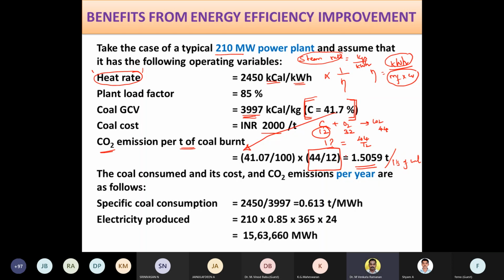Now, the heat content of the coal is 3,997. The heat rate required is 2,450, accounting for all efficiency factors. So the quantity of coal I should supply is based on 2,450 being the heat I need, as against 3,997 available with the coal. So 0.613 kgs of coal is required for generating 1 unit of electricity. If you multiply by 1000, you'll get it as tons per MWH.